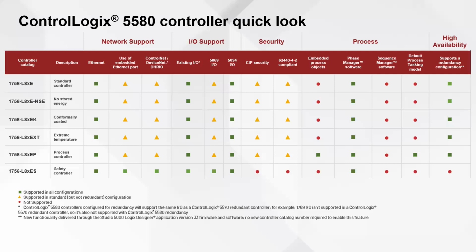One thing I didn't discuss there was, when you looked at the L5 and L6 processors, you had a battery. When we moved to the L7 family, there was no battery. We used what was called a stored energy device. It was basically a capacitor that could hold the RAM up long enough to allow it to move the program into a non-volatile memory space.